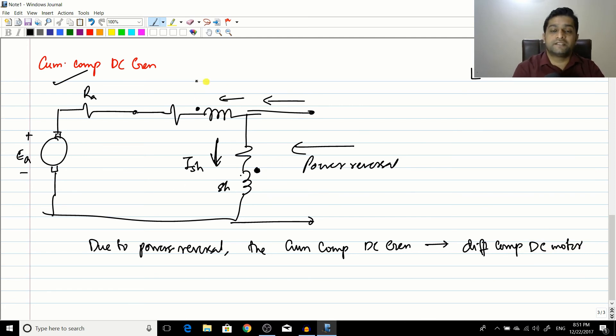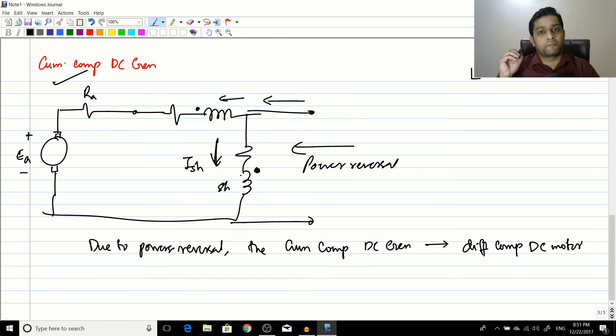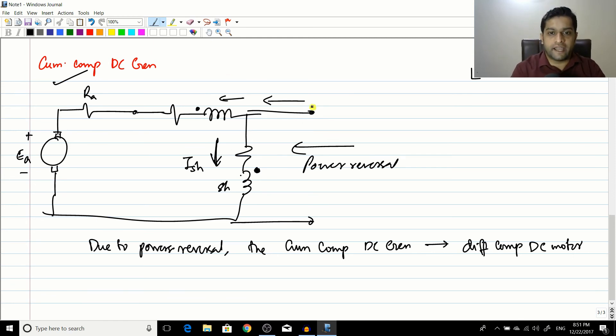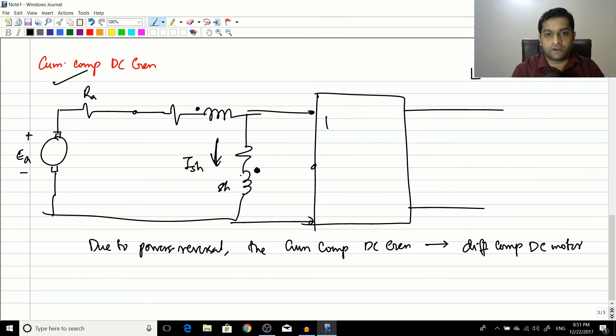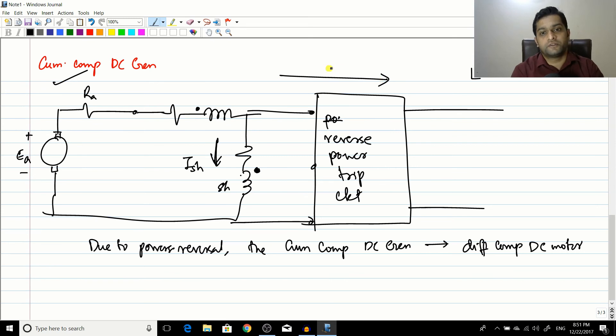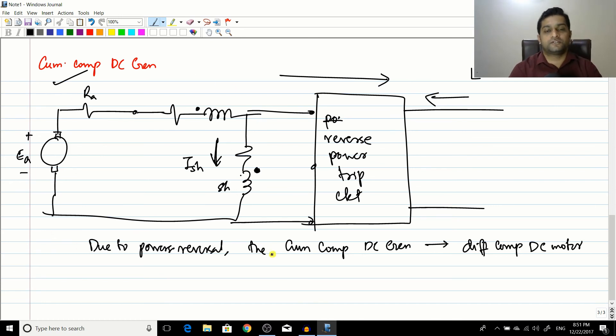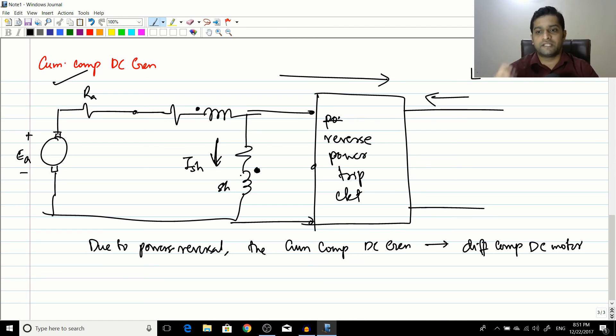This is a dangerous condition because the generator now has all the problems of the differential motor. To protect against this, such generators are equipped with a reverse power trip circuit. When power flows normally out of the generator, the circuit allows it. But when power flows in the reverse direction, this circuit trips the entire DC generator so it does not become a differentially compound DC motor.